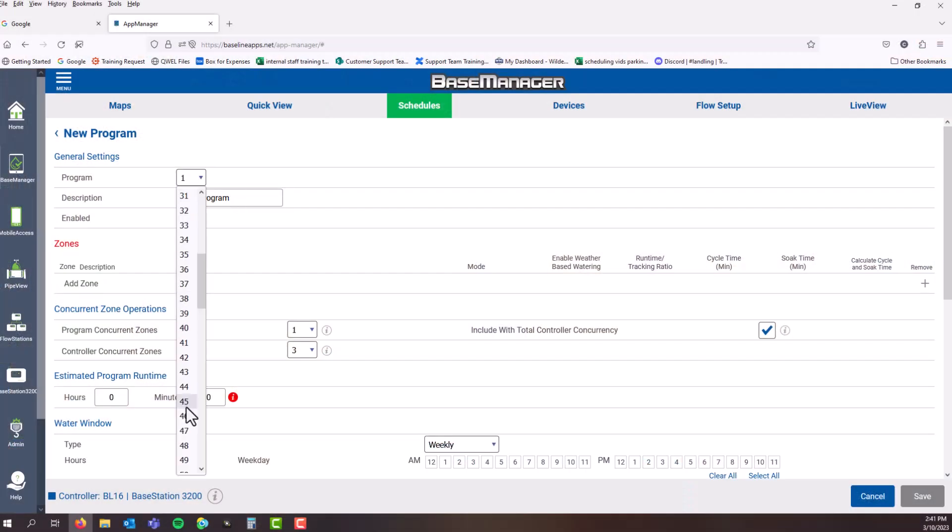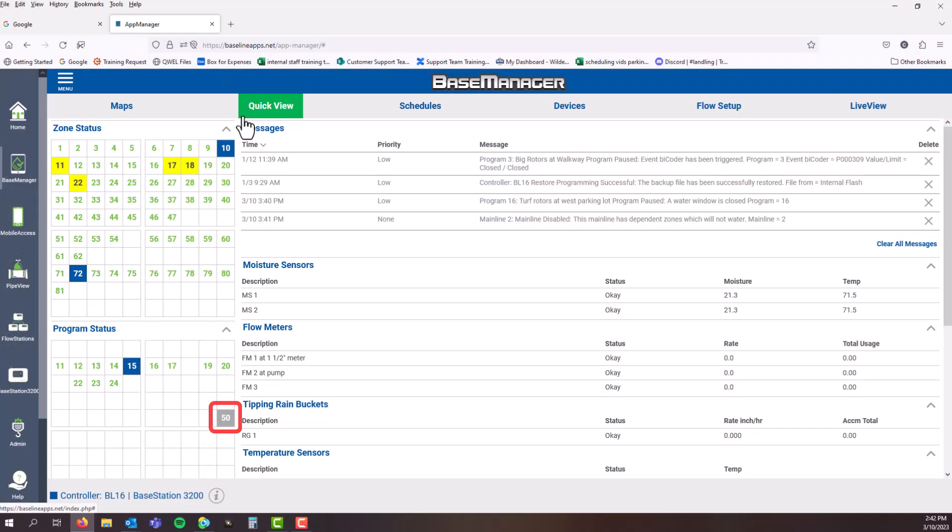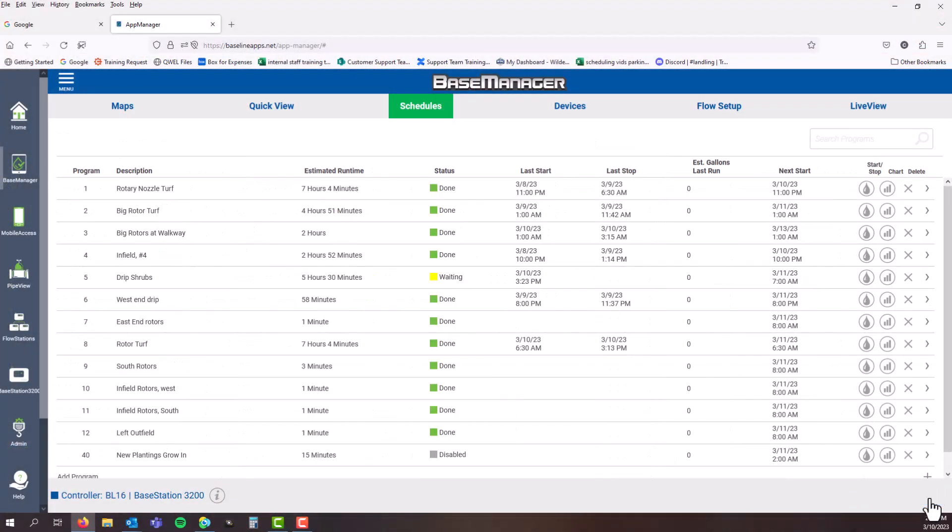If I have a program I'm going to use once or twice a year — maybe a special blowout program or a plant establishment program — I don't want anyone to accidentally run that. So I'll make it way down at the bottom, program 90 or 99. That'd be the only time we manually click it and run it. It's not mixed in with the bulk of the others on QuickView. I use those lower numbers, the 90s to 99s, for cistern starts, pump starts — extraordinary stuff I don't want in the main group. If you put them at 99, people tend to ignore them, but it gives you lots of room. On QuickView we'll have some gaps in between. We'll also talk about leaving gaps when we get to zones.